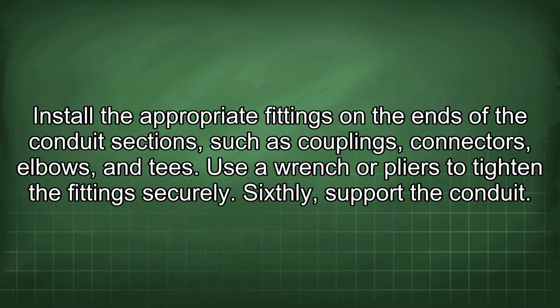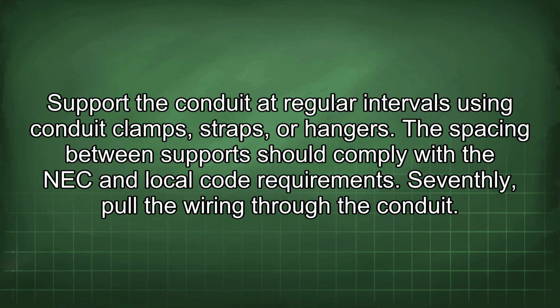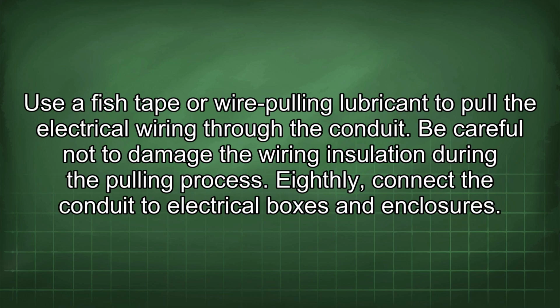Sixthly, support the conduit. Support the conduit at regular intervals using conduit clamps, straps, or hangers. The spacing between supports should comply with the NEC and local code requirements. Seventhly, pull the wiring through the conduit. Use fish tape or wire pulling lubricant to pull the electrical wiring through the conduit. Be careful not to damage the wiring insulation during the pulling process.